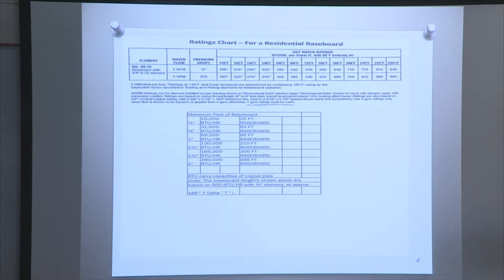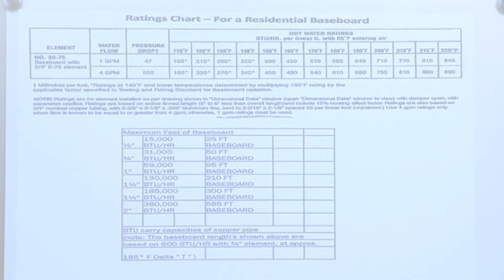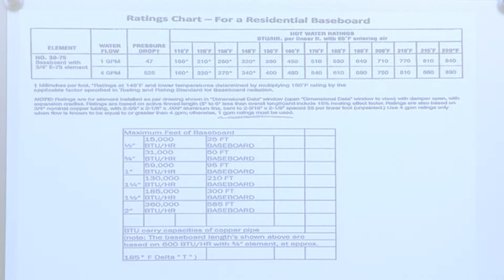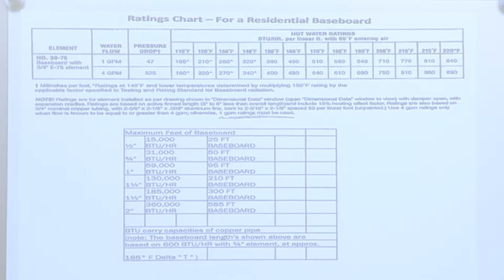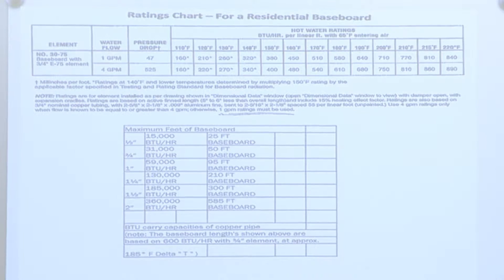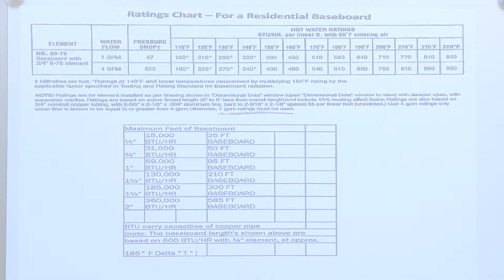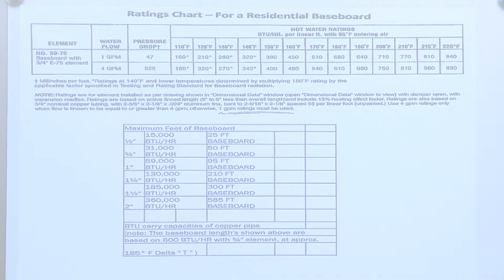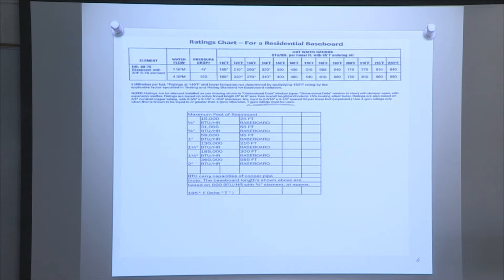Here's one of the rating charts. There are many of them — manufacturers have all different types. You can see the maximum feet of baseboard; for a half-inch pipe at 15,000 BTU, the maximum is 25 feet. The note at the bottom states that the baseboard lengths shown are based on 600 BTUs per hour with a three-quarter inch element at approximately 185 degrees delta T.